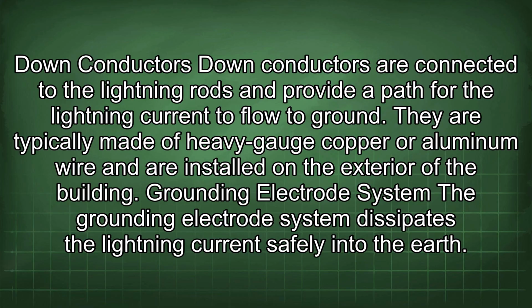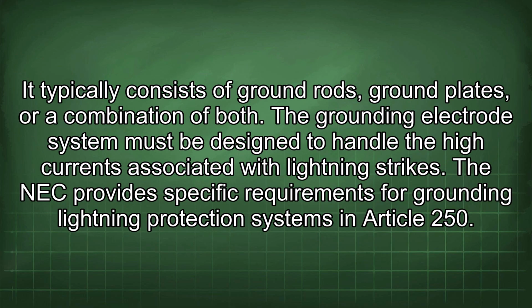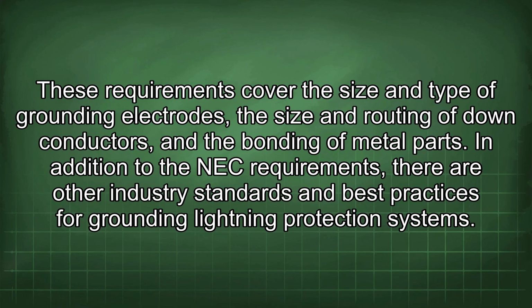Grounding electrode system. The grounding electrode system dissipates the lightning current safely into the earth. It typically consists of ground rods, ground plates, or a combination of both. The grounding electrode system must be designed to handle the high currents associated with lightning strikes. The NEC provides specific requirements for grounding lightning protection systems in Article 250. These requirements cover the size and type of grounding electrodes, the size and routing of down conductors, and the bonding of metal parts.